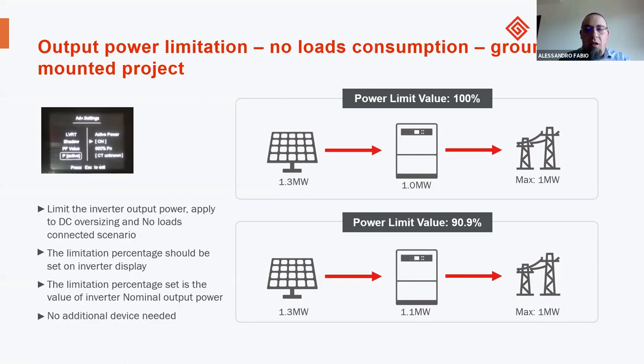In the case that you have, for example, a limit of one megawatt for a PV system of 1.3 megawatt on the DC side, you can limit to 1 megawatt. But if you don't have a limitation, you can, for example, put more power into the grid if you need it, if you have the possibility. I don't know if in Greece it's possible, it depends on the norm, but we have this option for this function.